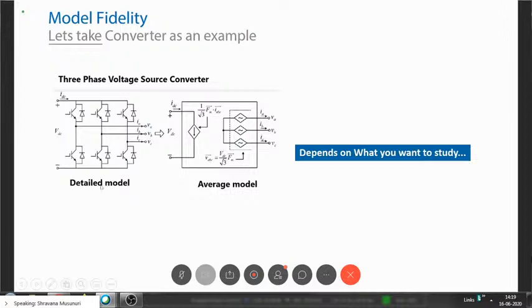A detailed model is typically good for power quality applications, or if we want to study something wrong in the switch, like if one of the switches fails, which is a common failure mode in UPS systems or inverters, to see how the system reacts. If you're more interested in instantaneous responses versus average model, where you're developing a converter not looking at high resolution data but at the average level over a cycle, then select accordingly so that your study has applicability. The kind of model you select will determine the applicability of what you want to study.